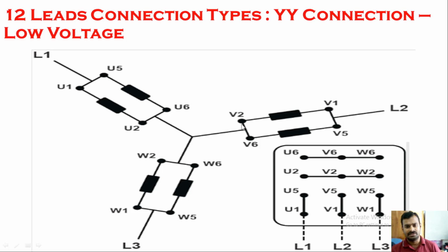So you can decide. If you want it in a star connection, you will short U2 U6, V2 V6, W2 W6 first, and these will be connected, shorted to each other, and U1 U5 is shorted and it is connected to L1. So this is for the low voltage configuration I am speaking about, and V1 V5 is shorted and connected to L2, W1 W5 is shorted and connected to L3. So this is the wiring configuration for 12 lead connection type star connection low voltage.